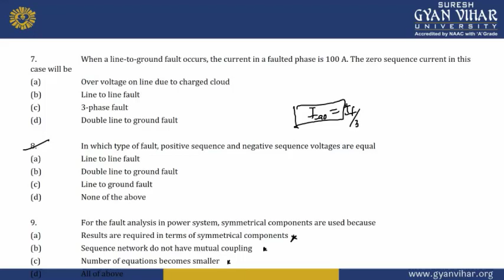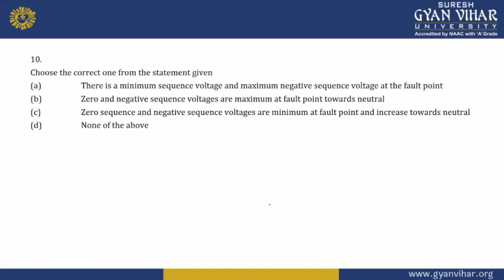We will discuss it. I'm leaving it up to you. Choose the correct one from the given statements. Option A: there is a minimum positive sequence voltage and maximum negative sequence voltage at the fault point. Option B: zero and negative sequence voltages are maximum at the fault point and decrease towards the neutral. Option C: the zero sequence and negative sequence voltages are minimum at the fault point and increase towards the neutral. And option D is none of the above.